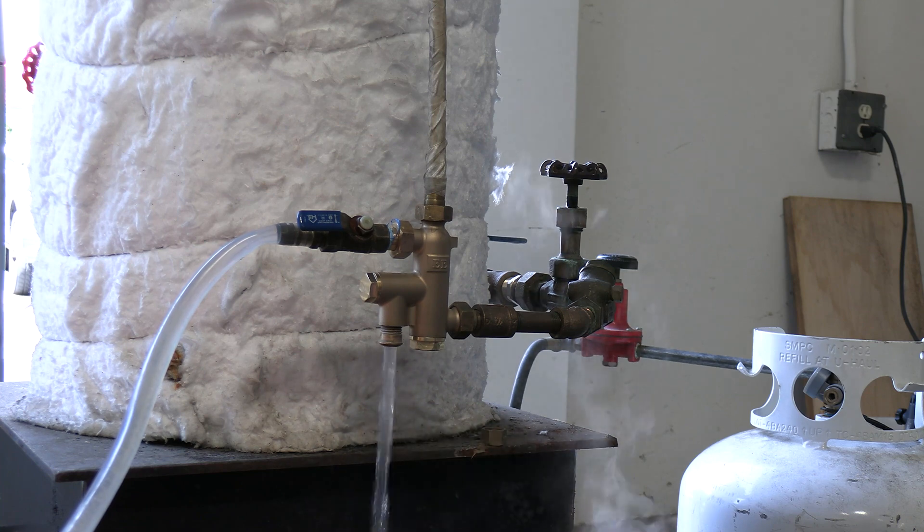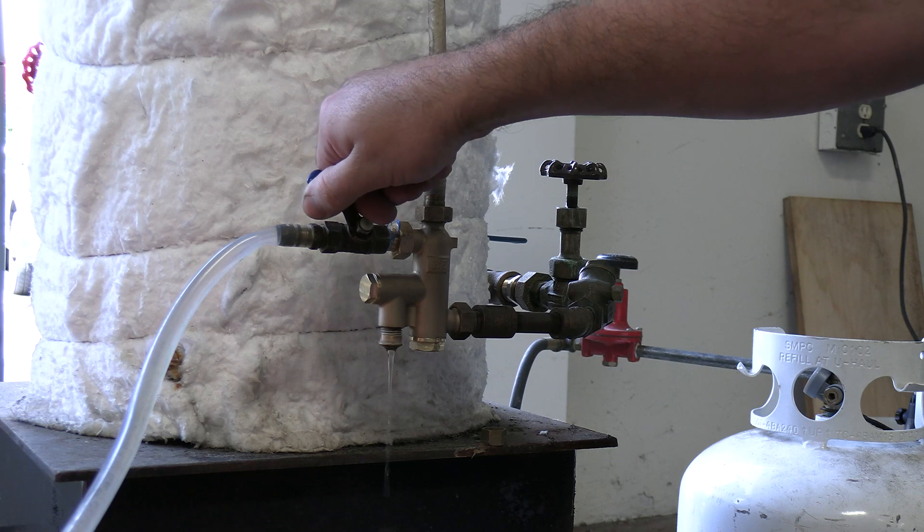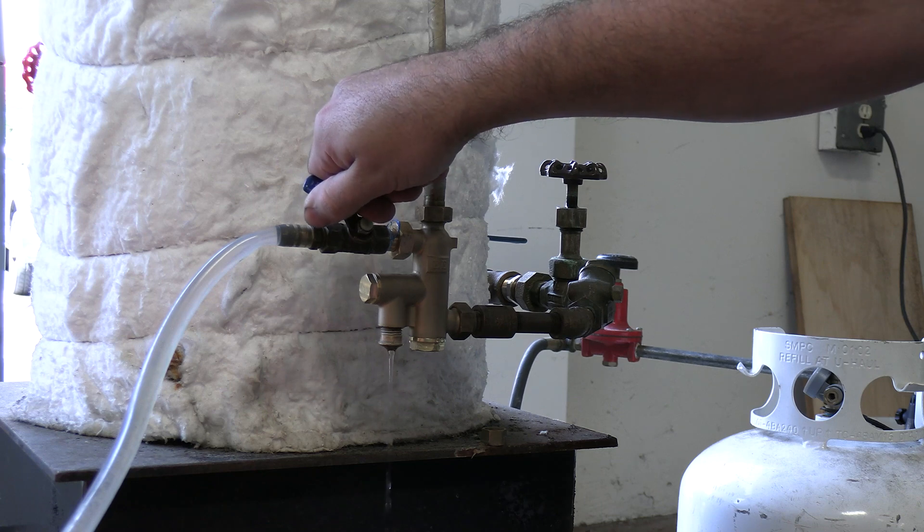When you start to get above the injector's maximum operating pressure, you will notice it start to drip. It is still injecting, but with some waste, no matter how you adjust the water valve.